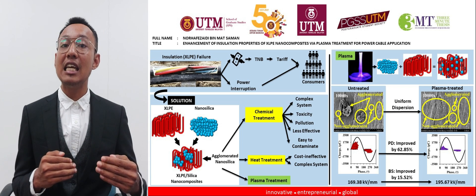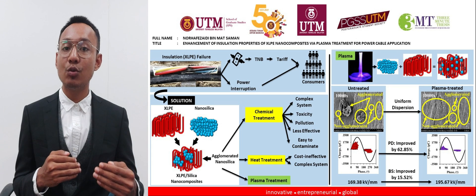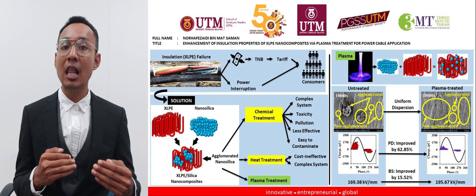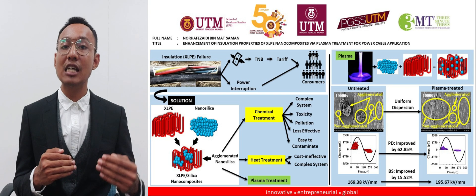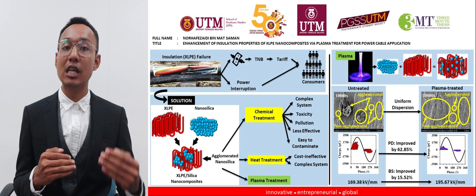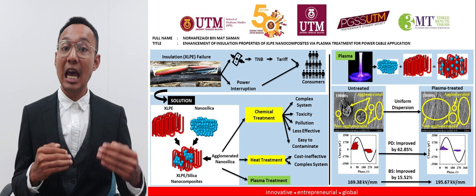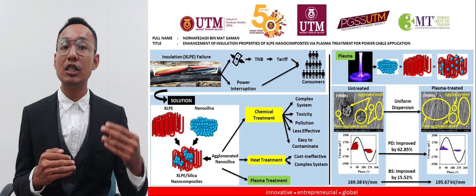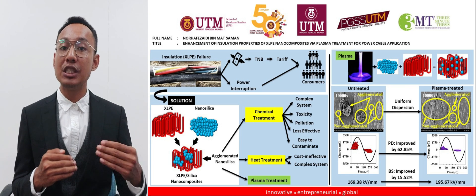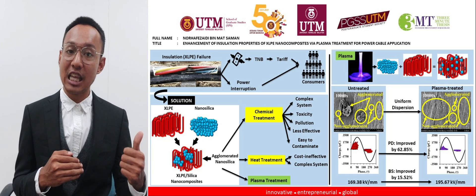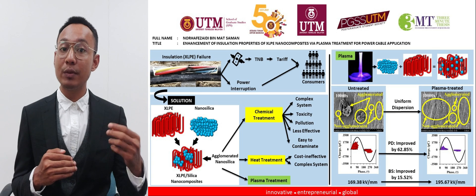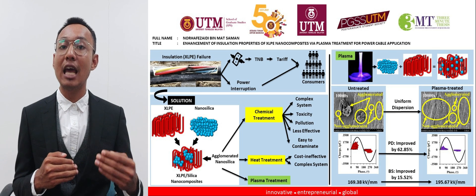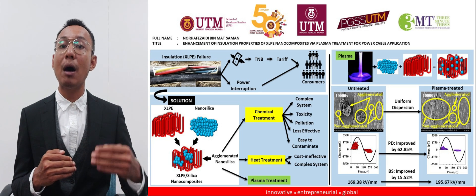Recently, research has been conducted to improve the properties of XLPE insulation cable by introducing nanometer-size silicon dioxide into the XLPE. The main idea is to improve two main insulation properties of XLPE, which are partial discharge and breakdown strength, both of which are indicators of the performance and lifetime of power cables.